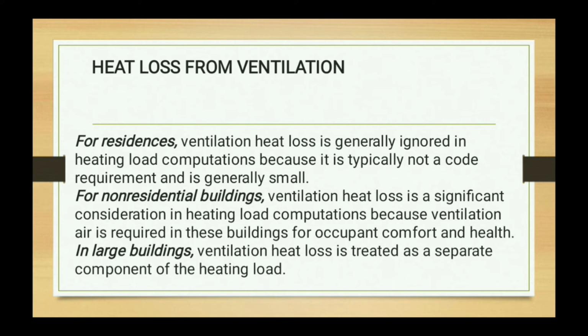So, for residences, yung ventilation heat loss daw ay ini-ignore lang sa heating load computation. Kasi nga, it is not a code requirement and it is generally small. While the non-residential buildings daw, yung ventilation heat loss daw ay may significant consideration sa heating load computation. Kasi yung ventilation air is required sa mga buildings for occupant comfort and health. So, in large buildings naman, yung ventilation heat loss daw ay tinatrato or treated as a separate component of heat load.